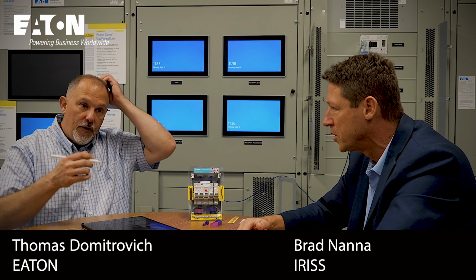The arc flash boundary is the big challenge when doing thermography. It's not necessarily the few seconds it takes to get a picture, it's getting dressed up, then undressing. You got to get dressed, get all that stuff off, get in to do your snap, finish, and then button it all back up. There's a lot of time involved for every single termination.